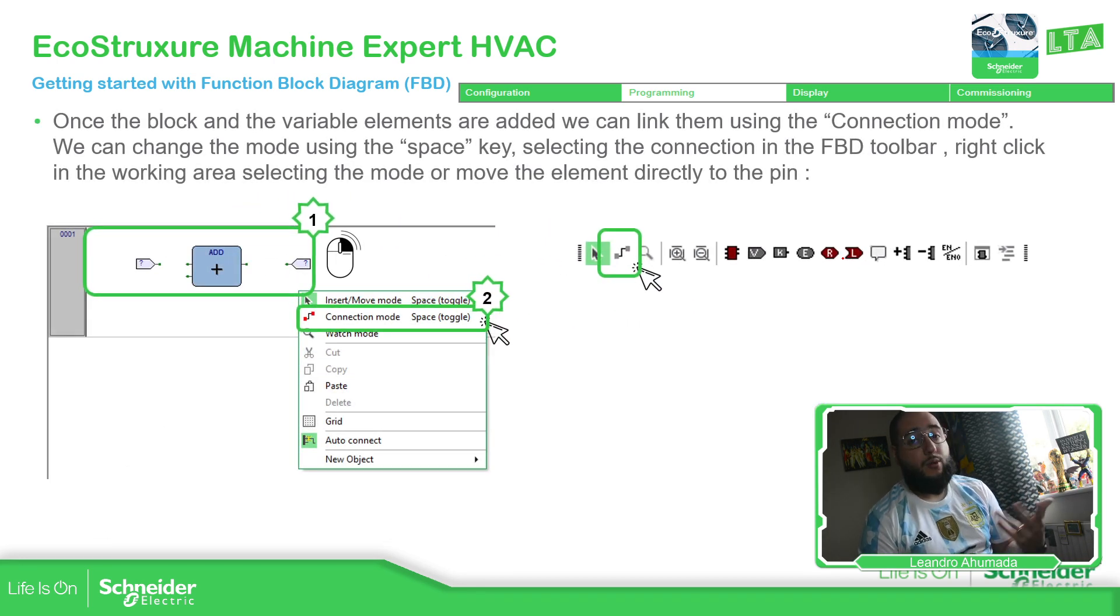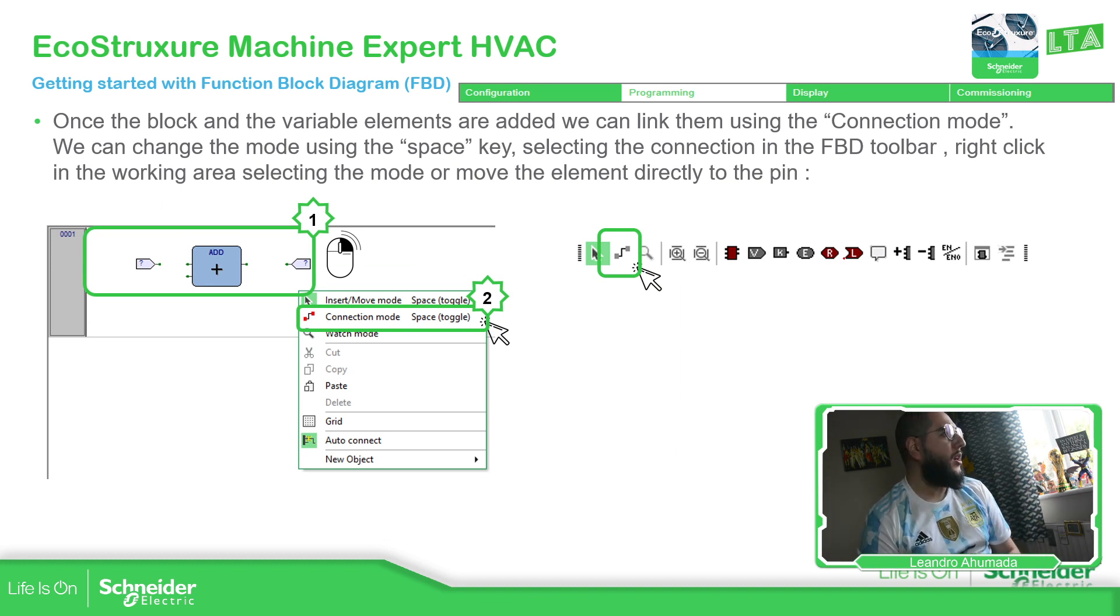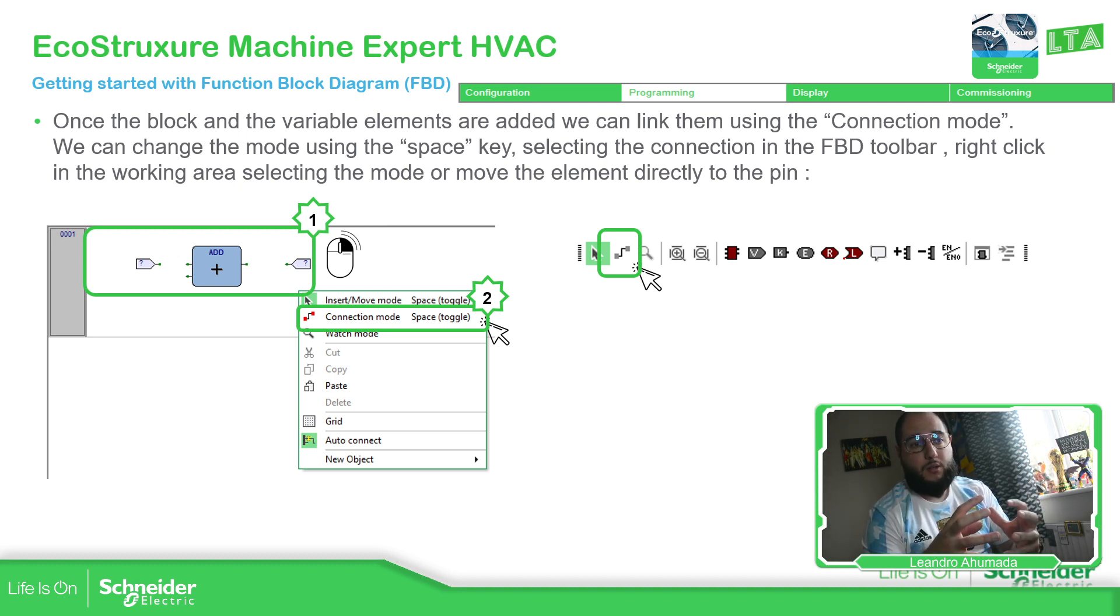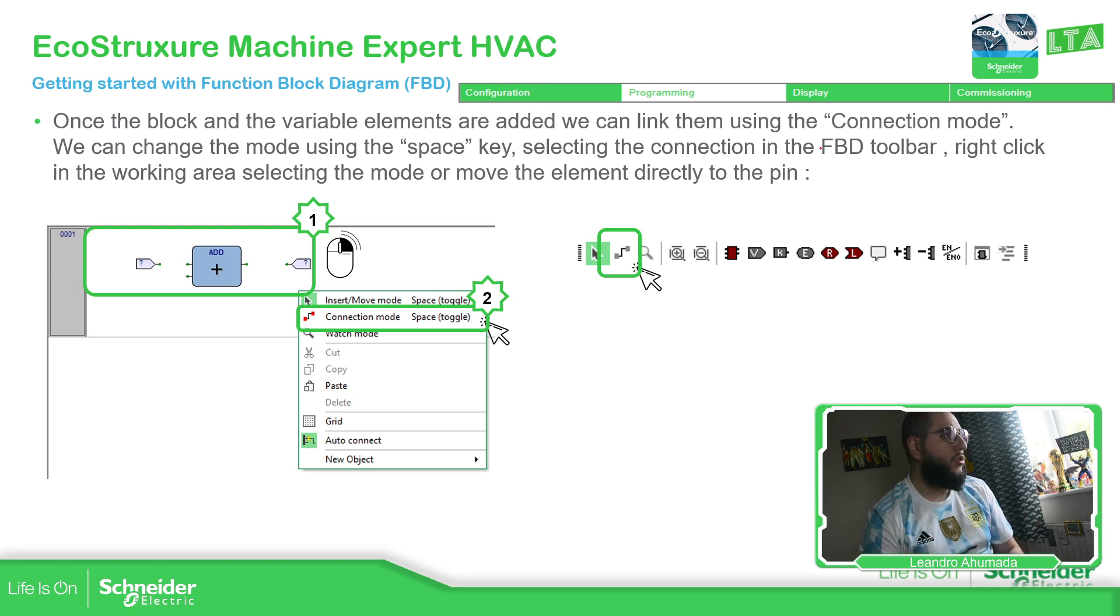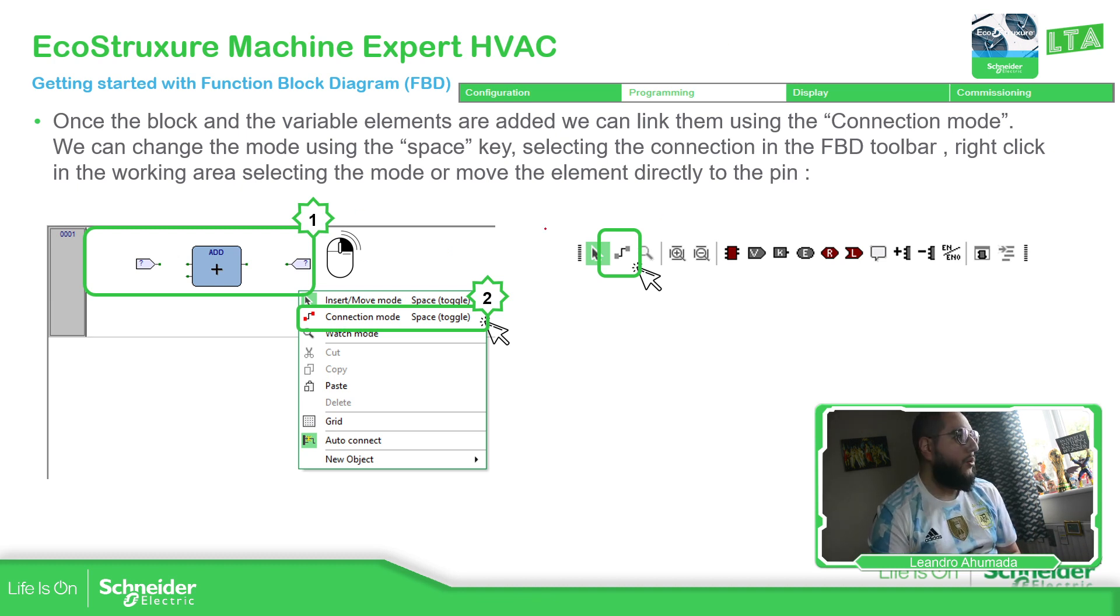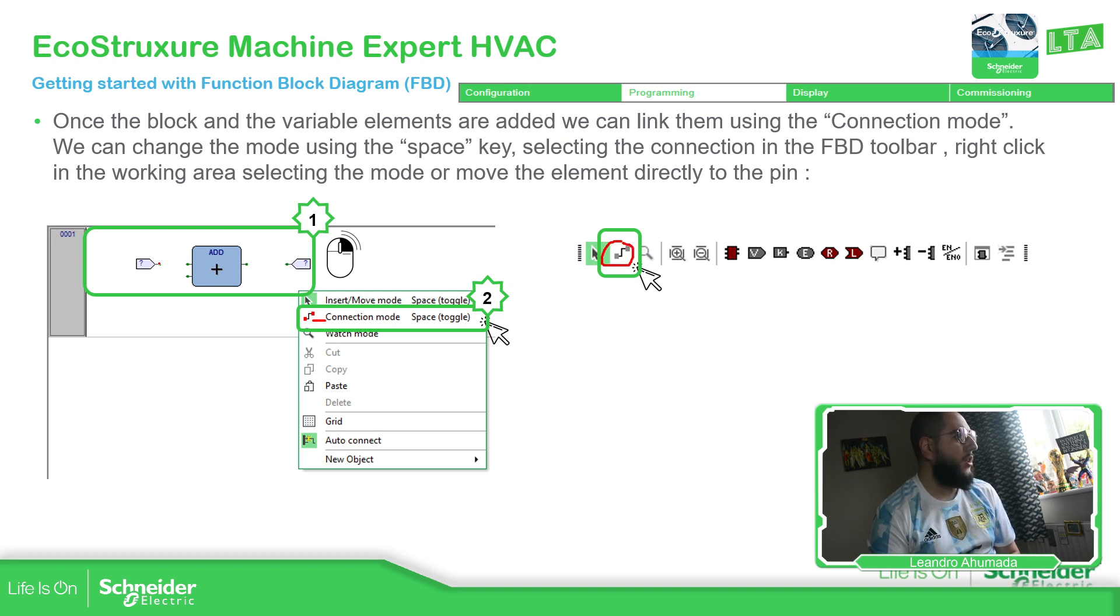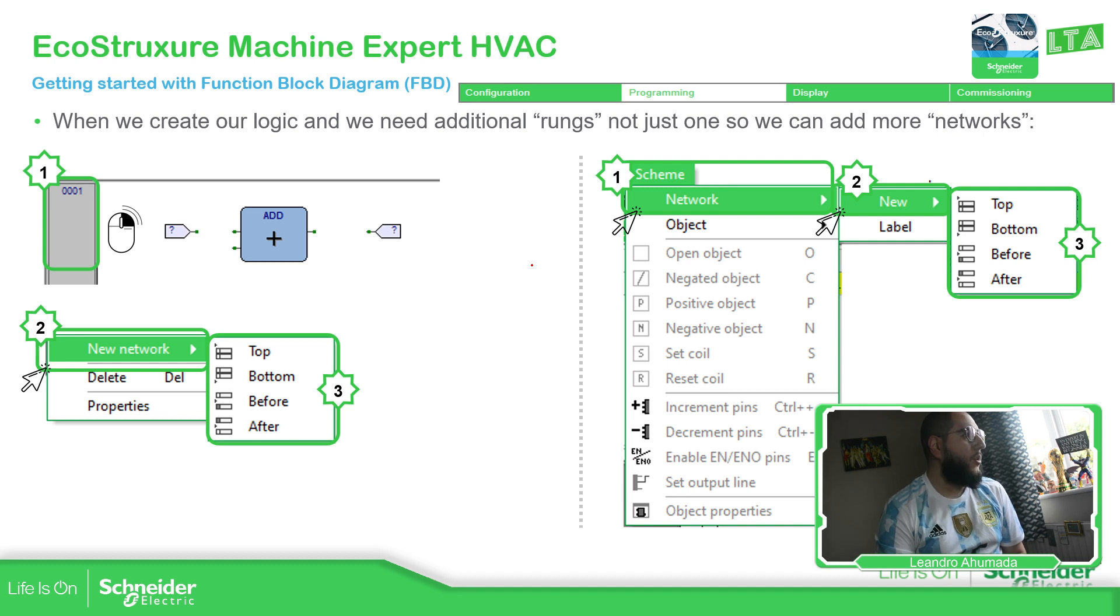You will need to know which function block to use, but we want to cover that later. So now we have the object variables. We have the function block. Now in order to link this, what we need to do is to change the mode from insert mode to connection mode. You can use the space bar or you can right click and select this connection mode, or on the toolbar, select this one, which is the one that links. So you just need to link from here to here and from here to here. Simple as that. It's not that difficult.